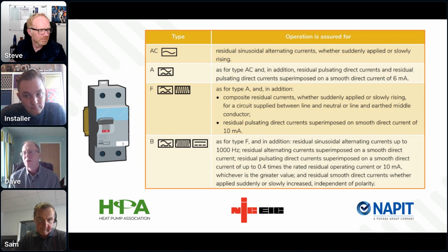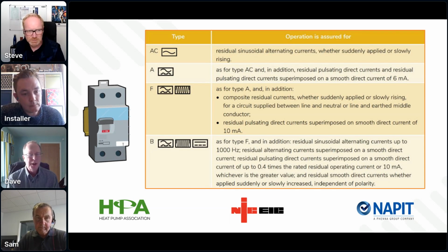Just to finish the story on type B plus, one of the comments in the chat is about type B HP. There is a product on the marketplace which is marked HP for heat pump, and just to be clear, that is not a B plus. The type B HP, which is branding from a particular manufacturer, is a type B as recognised in BS 7671. It has been tested and approved against the UK product standard and is in line with BS 7671. But the HP is their indication that it's been specified for heat pumps.